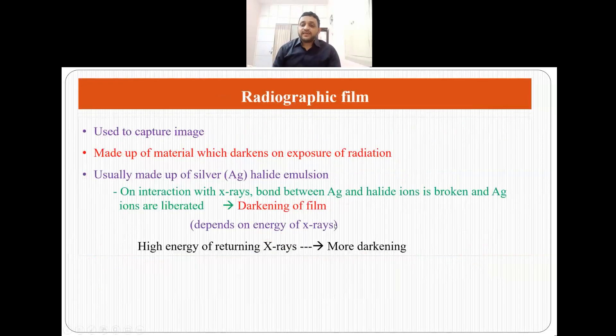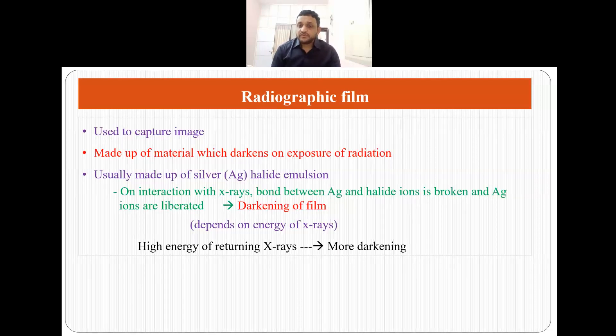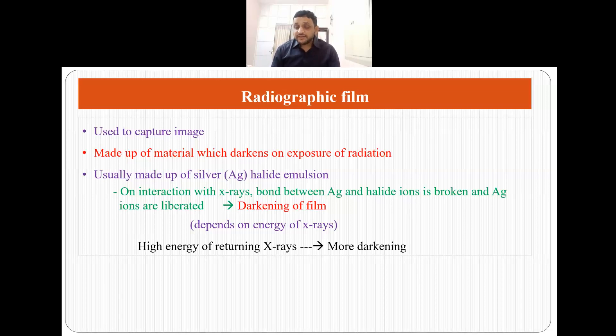The second important thing in radiography is the radiographic film, which is used to capture images. It must be made up of material that darkens when exposed to radiation. That is why the radiographic film is made up of silver halide emulsions. When silver halide emulsions interact with x-rays, the bond between silver and halide ions is broken, silver ions are liberated, and we get darkening of the film. This darkening depends on the energy of x-rays — higher energy means more darkening, lesser energy means less darkening.